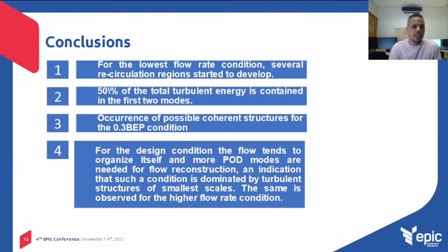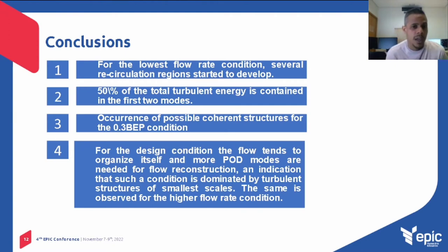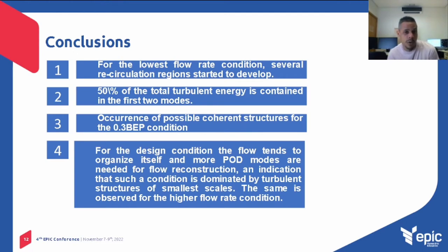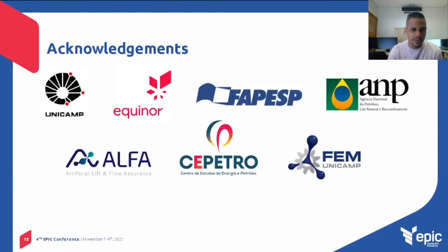As conclusion, for the lowest flow rate condition, several recirculation regions start to develop. For the 0.3 BEP, 50% of the total turbulent energy is contained in the first two modes. Also at 0.3 BEP, we observe the occurrence of possible coherent structures of the flow. For the design condition, the flow tends to organize itself and more POD modes are needed for flow reconstruction, indicating that such a condition is dominated by turbulent structures of smaller scales. The same is observed for the high flow rate condition. Thank you very much.